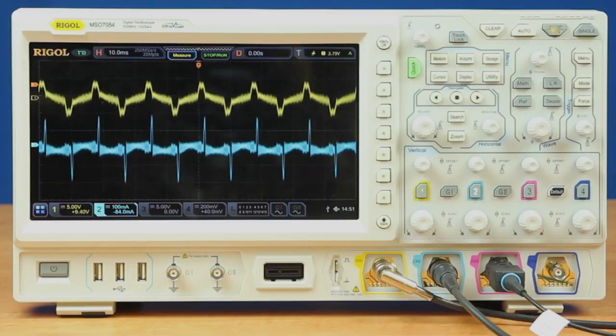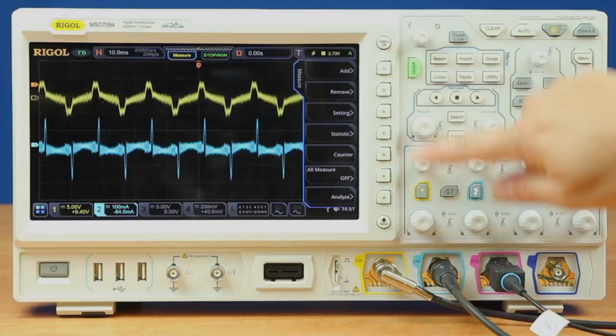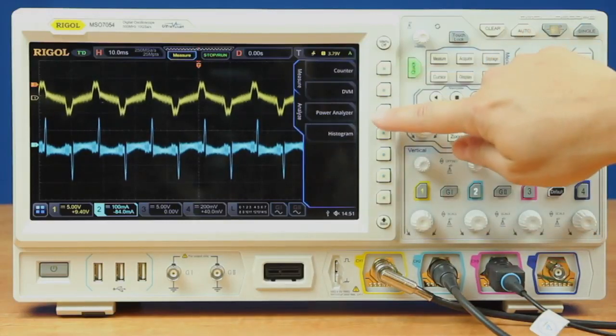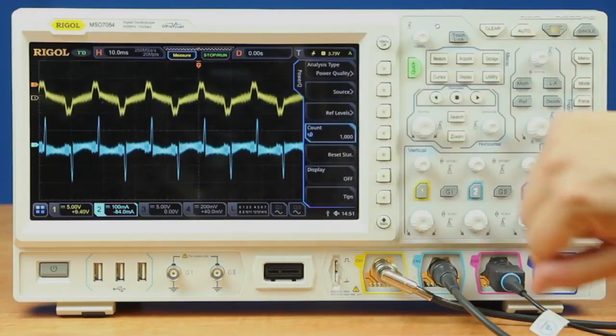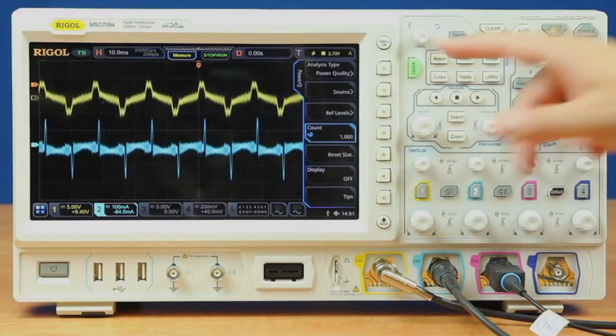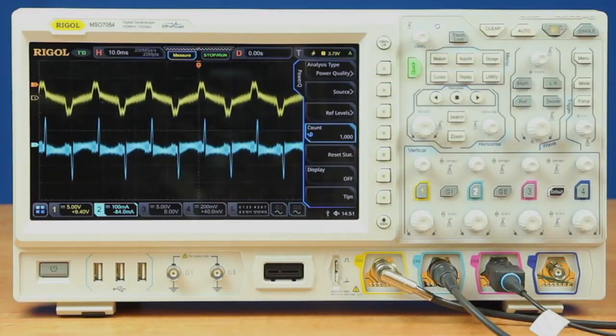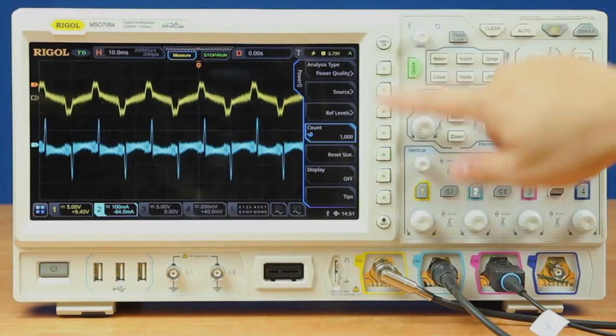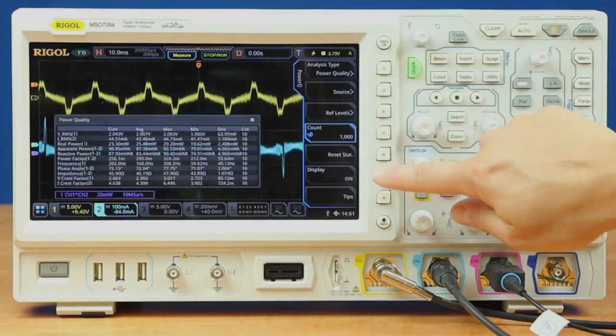To do that we're going to start with the power analysis capabilities built into the instrument. We go into the measure and analyze, power analyzer. First thing we're going to do is called power quality measurement. So we're going to go ahead and turn that on.